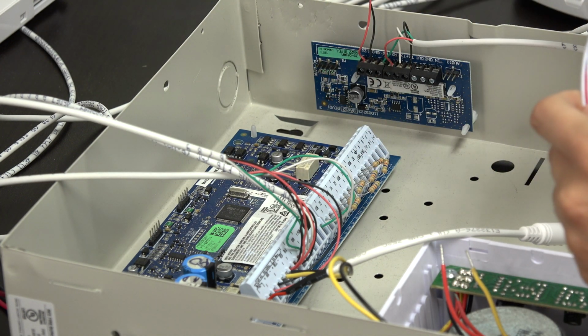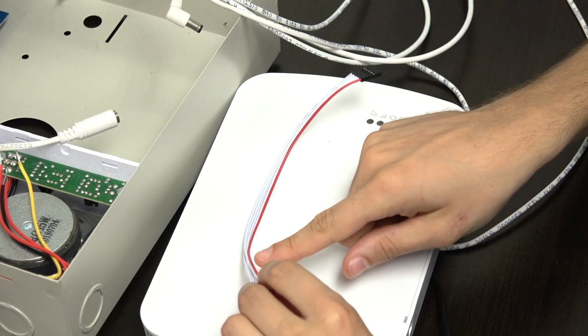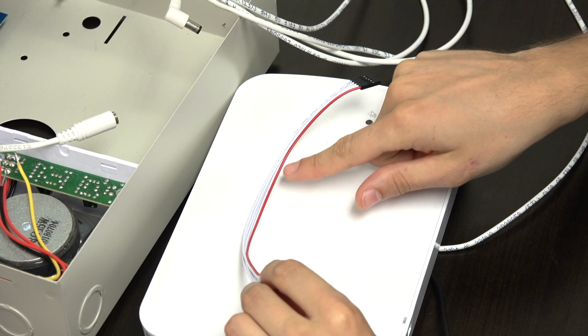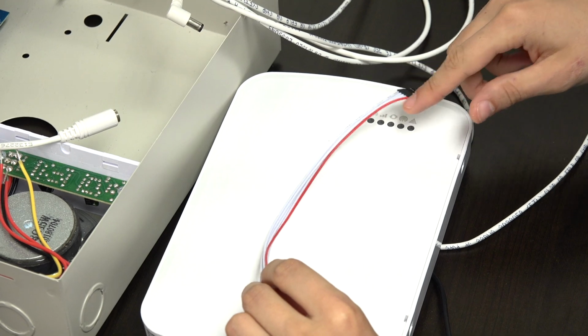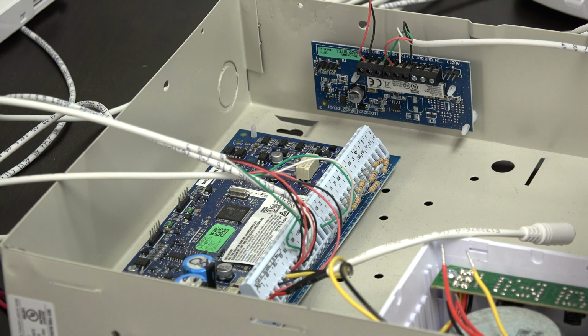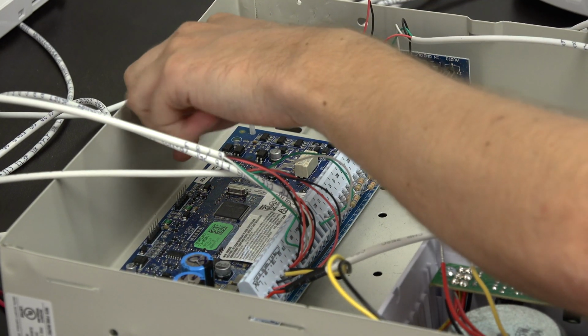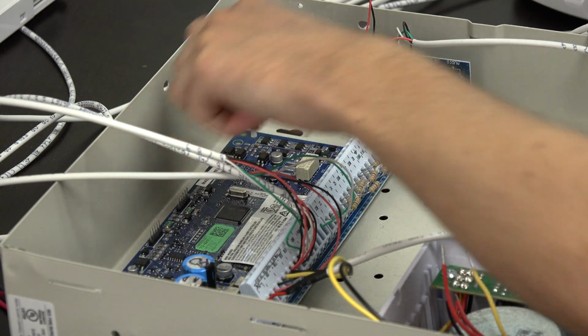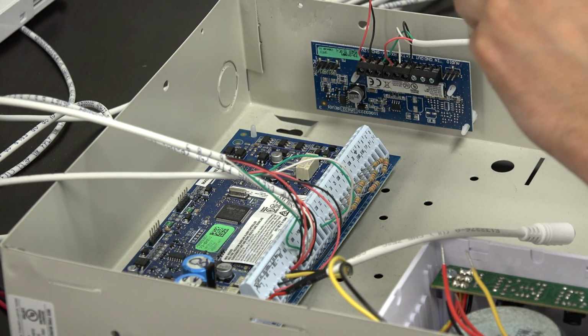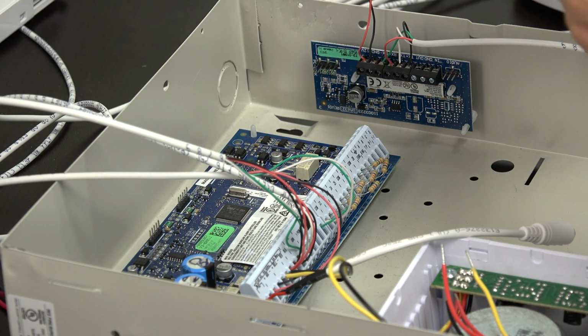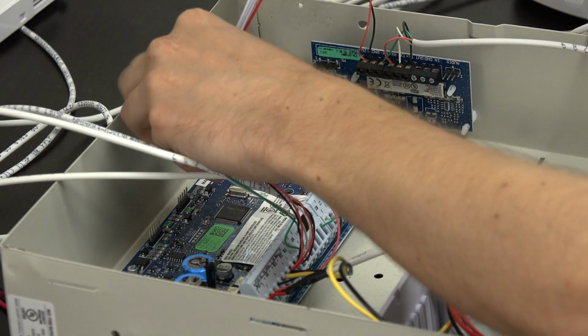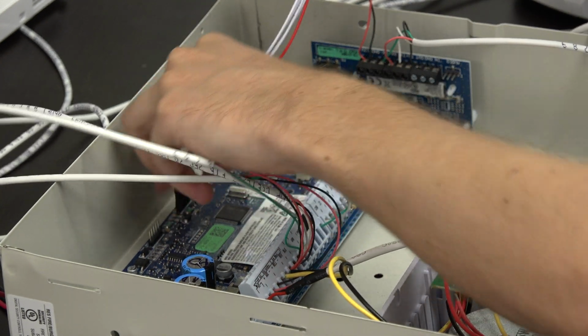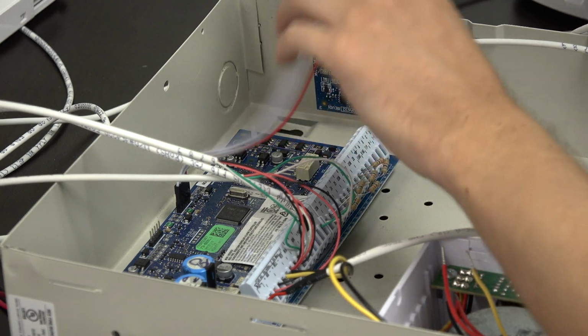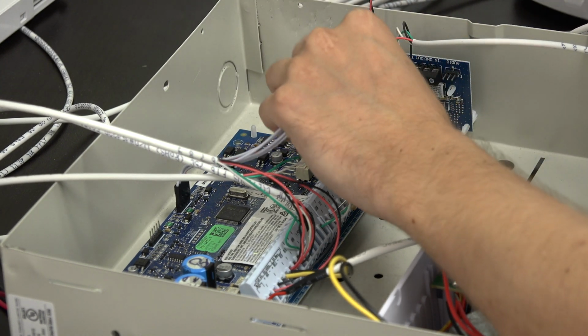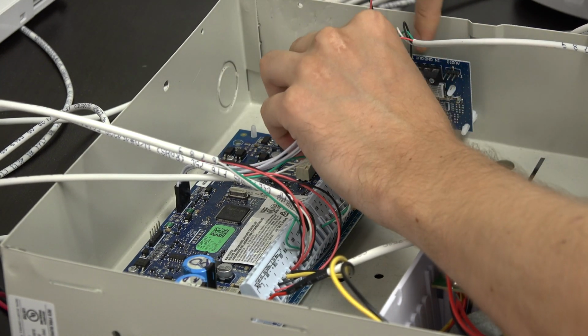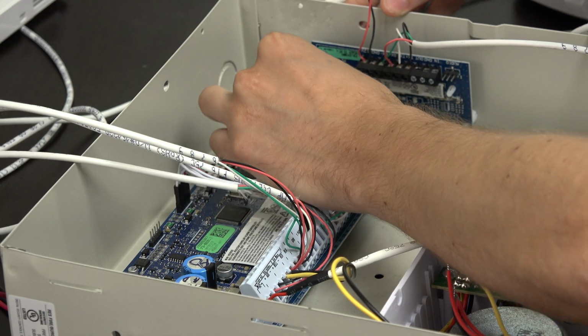Now, you may notice that there is one red wire on the PC link cable. So that actually determines which way you plug it in. So the way I like to remember it is you see that it has the word red on the right. You're going to have the red on the right for this connection over here. So you just have it with the red on the right side, and you just insert it in. And then at the PCL422, you have the red closest to the terminal block. So you just have it right in there.